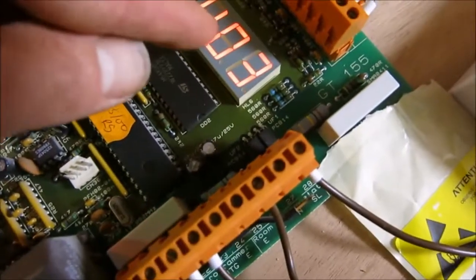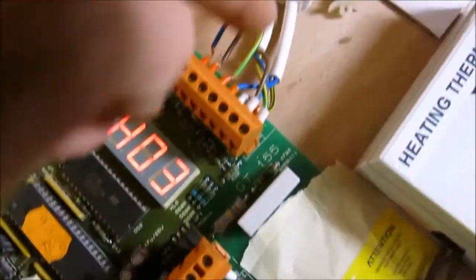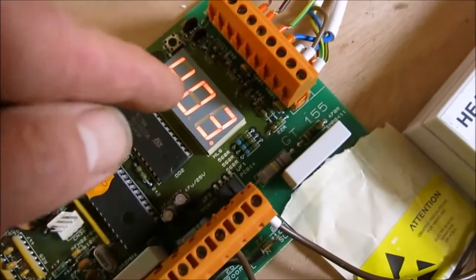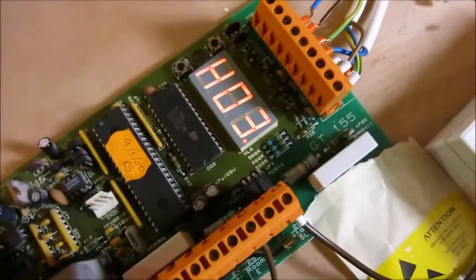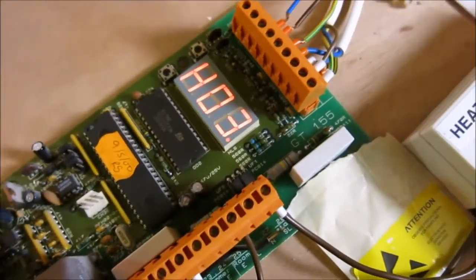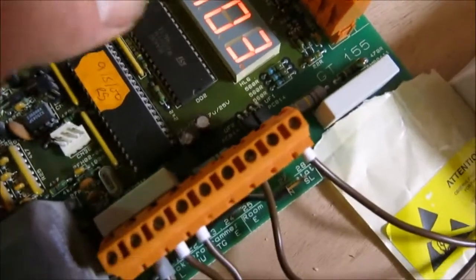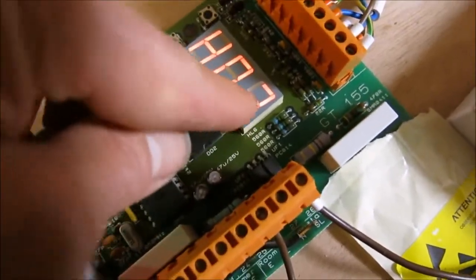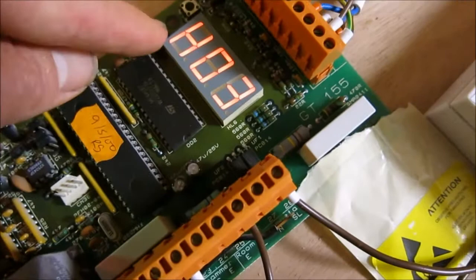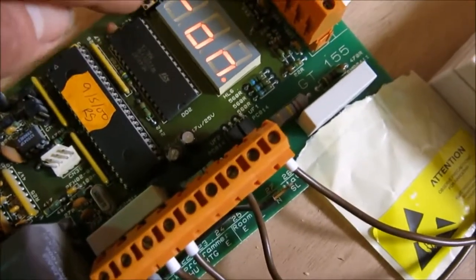If any of those show -er, then you've either got a problem with the wiring or the actual thermistor itself is shot through. They are a solid state thermistor, so they've got electronic devices in them. Just the same, if say this one was reading 99 degrees or something stupid like that, then that's clearly an indication that something's not right. You press it again, by the way, you go back to the beginning again.